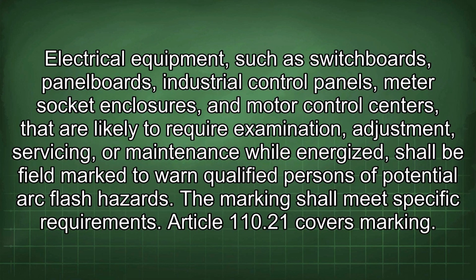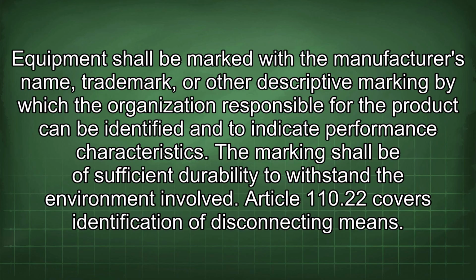Electrical equipment such as switchboards, panelboards, industrial control panels, meter socket enclosures, and motor control centers that are likely to require examination, adjustment, servicing, or maintenance while energized shall be field marked to warn qualified persons of potential arc flash hazards. The marking shall meet specific requirements. Article 110.21 covers marking. Equipment shall be marked with the manufacturer's name, trademark, or other descriptive marking by which the organization responsible for the product can be identified and to indicate performance characteristics. The marking shall be of sufficient durability to withstand the environment involved.